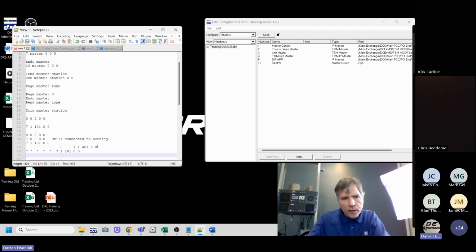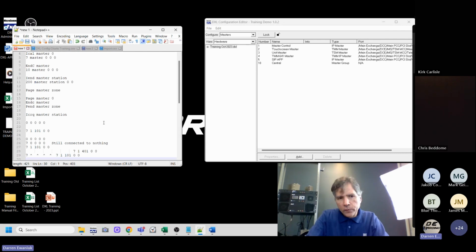So just a note on that: almost all drivers, all DA servers that I'm aware of, will do it as a single block. If you're using a PLC to communicate PLC to PLC and you use a block write command, it should work. But sometimes you might not have an option for a block write. So if you do single registers, write the first register, the command register, last. So that's one note on that.